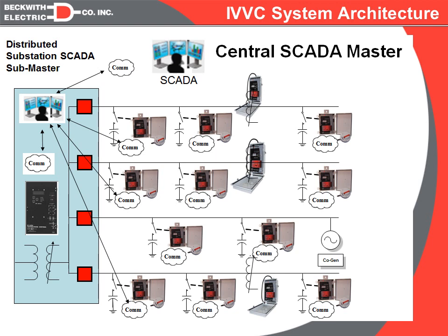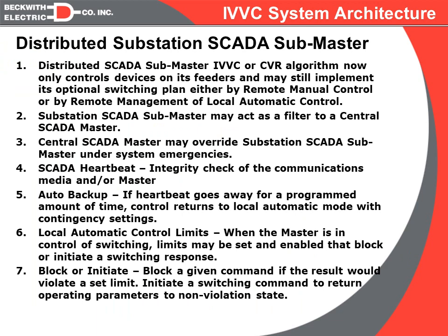So this is an area where we would want to use the direct heartbeat. Now, a disadvantage of the direct heartbeat is it does require a dedicated message from the SCADA system to each individual control, and therefore that is going to eat into the bandwidth requirements on our system. We still want to have the intelligence in the local controls. We still want to be able to block the SCADA commands just like before.